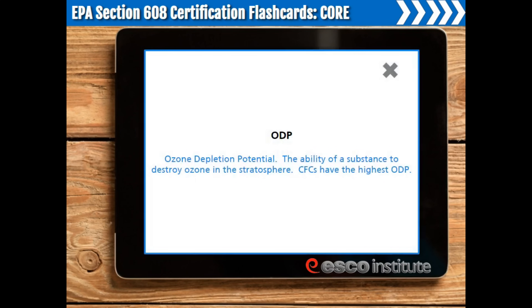ODP. ODP stands for ozone depletion potential — the ability of a substance to destroy ozone in the stratosphere. CFCs have the highest ODP. GWP. GWP stands for global warming potential. GWP provides a comparison of global warming impacts of different gases over a span of time. R-600a, an HC refrigerant, has a low GWP, while the GWP of R-410a compared to carbon dioxide is thousands of times greater.